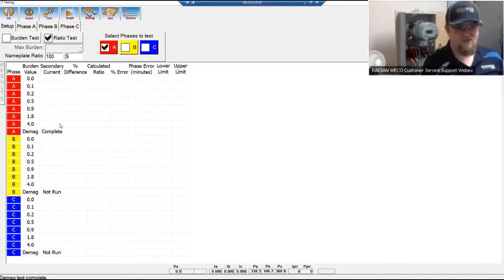Right below that is your tabs for setup and then each phase. For the setup tab, this is where we're going to set up exactly what we want to run on the RW. We can do a burden test, a ratio test, or both. Burden test is adding up to 4 ohms of burden onto the CT under test and seeing how the CT performs with excess burden in the circuit. Ratio test gives you a reading from primary current, a reading from secondary current, and then provides you the ratio determined by the primary and secondary current readings, giving you a ratio for the CT.